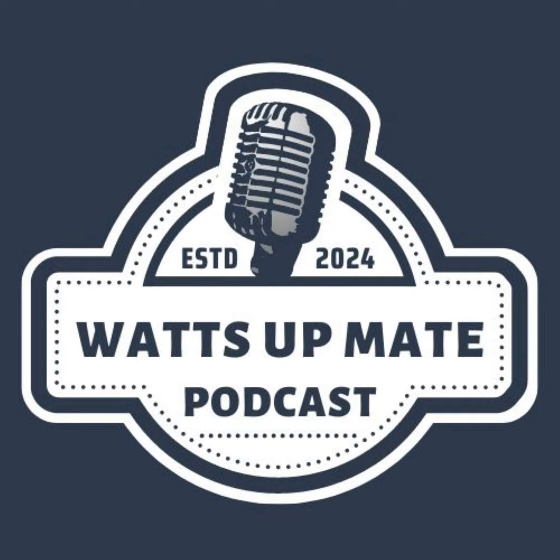Boom, you're lucky. It's a Friday arvo and you found a failed circuit breaker. You can swap that over and you're good to go home, right? Well, nearly. You still need to verify that the circuit is still safe to re-energise. Perhaps there was an overload issue or a short circuit that caused the breaker to internally trip, but it didn't trip the toggle, and now it won't reset.